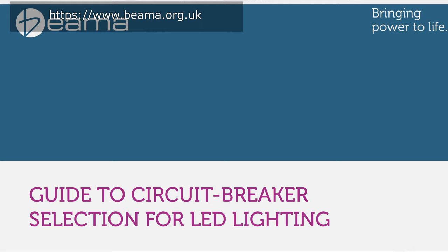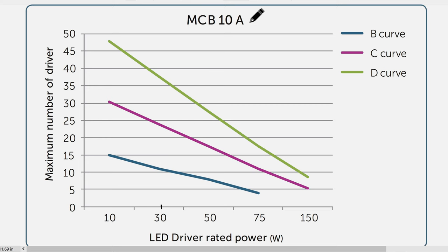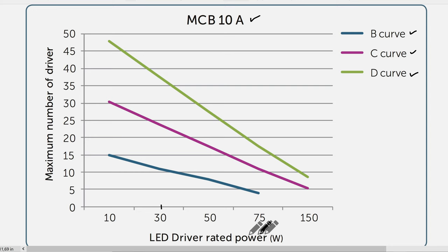I've located a guide to circuit breaker selection for LED lighting. In this guide they have a miniature circuit breaker of 10 amps, and three curves representing different types of circuit breakers. On the vertical axis we have the maximum number of drivers — the electronic driver circuit found inside the floodlight. On the horizontal axis we have the LED driver rating in watts. At 30 watts crossing the B curve, the maximum number of floodlights for a 10-amp miniature circuit breaker is only 11.